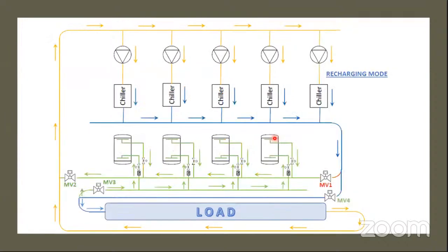And right after this, in recharge mode, the chiller has to cool the thermal storage tank also, and has to cool the load also from here. See, it is going to the load, and initially this is closed because the first priority is, of course, to satisfy the load.